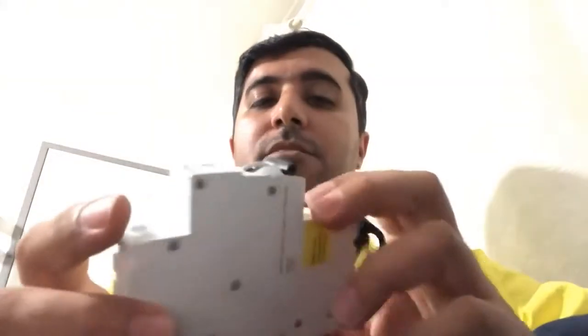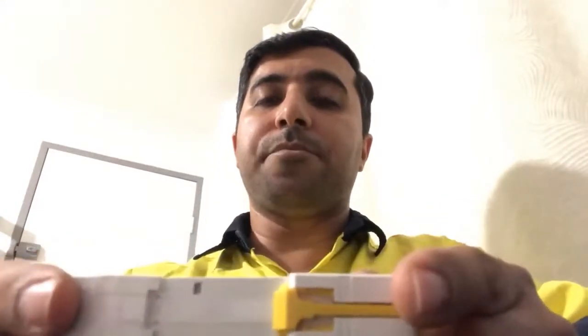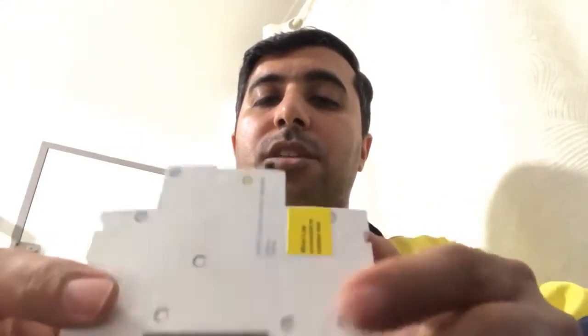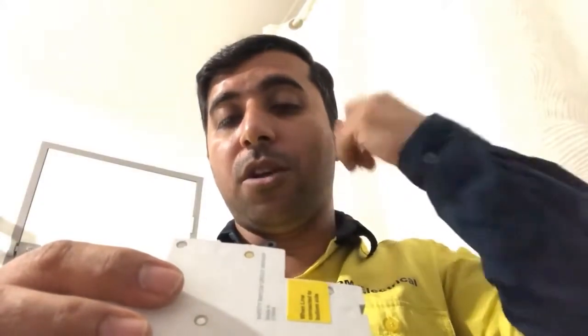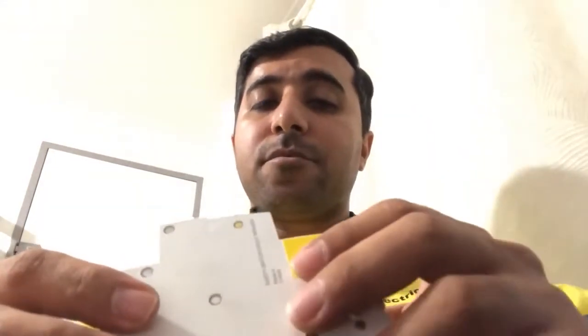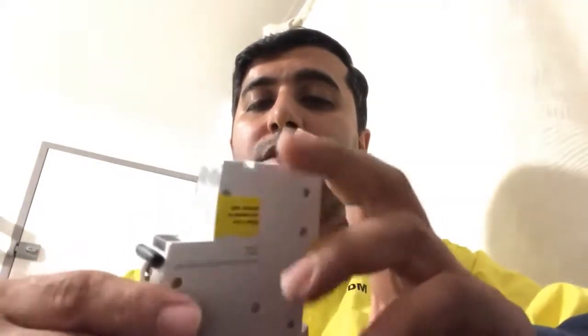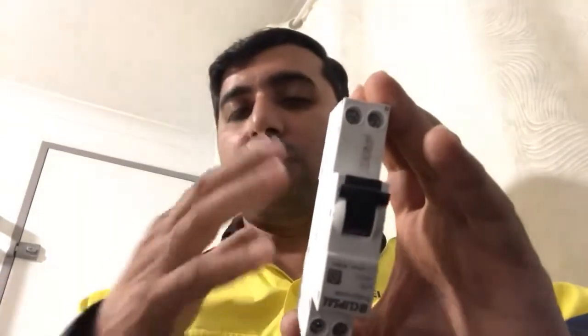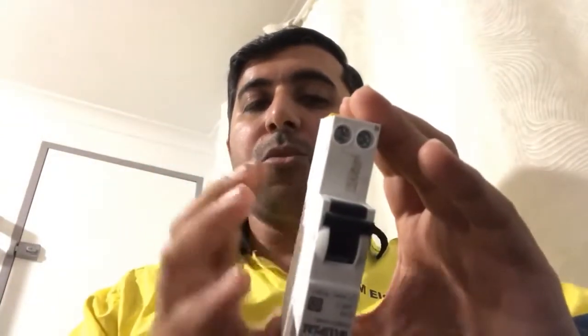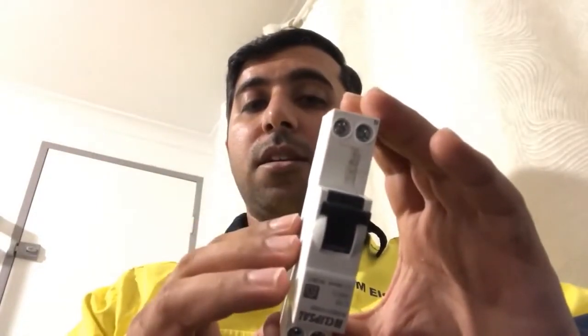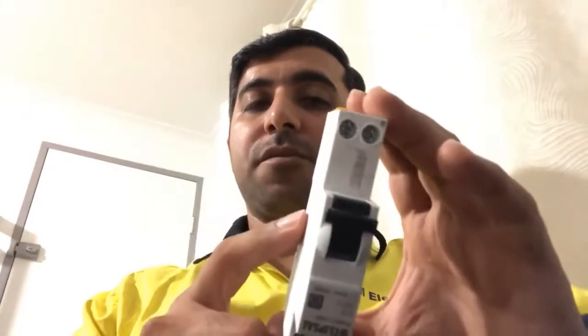Last but not least, what you need to know is that people usually think that whatever they see inside their switchboard, whether it's a safety switch, fuse, or circuit breaker, is there to protect their appliances or whatever they want to connect. That is not true. All the protective devices that you find inside the switchboard in the house are actually mainly there to protect your cable and the wiring inside the house, and stop them from getting damaged or overheated, or the insulation burning. So based on that, what I need to tell you is that the circuit breaker or any protective device inside the switchboard, which is connected to one set of wiring or two, they have to match with each other in terms of current capacity rating.